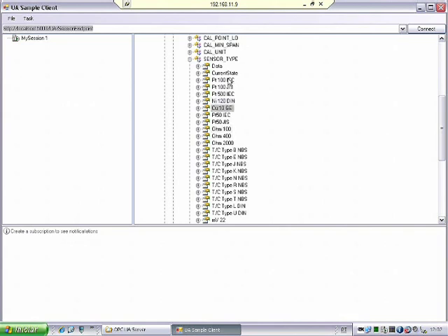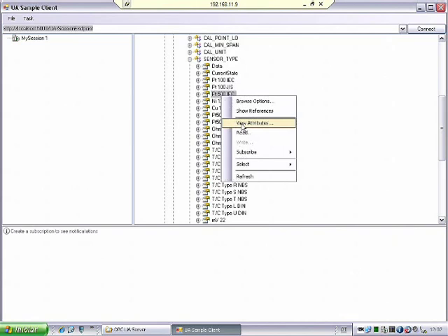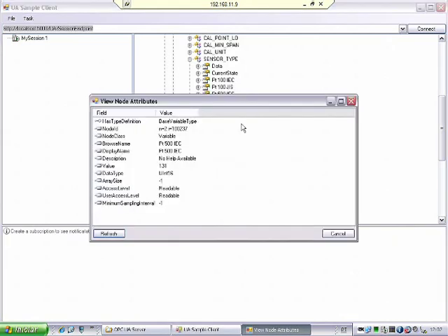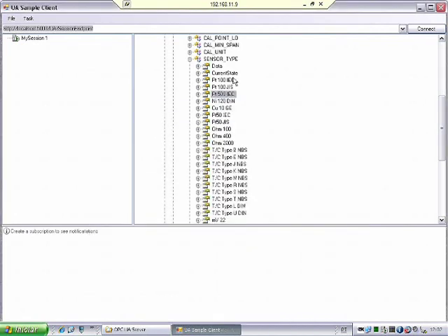So this is useful for writing, because I will not write a string. The operator is not going to write, I want a PT100 IEC. He is going to write the value. So with all the enumerations exposed in the address space, I am able to look what I want to write as the sensor type. And the server is going to send it to the device, and whenever it comes back, it's going to make the conversion back to me.